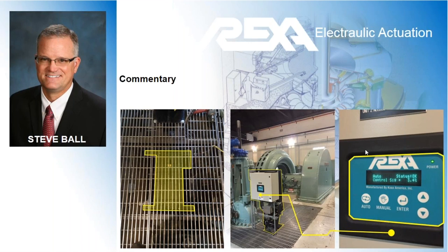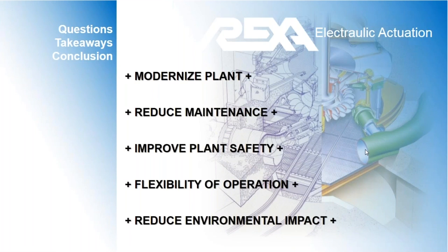We put another one of these together on the smaller plant on the other side of the Sierras, and its job was to modulate the power needle as well, with no governing, because it is a small unit tied to the system. It had a forebay up about 500 feet in elevation above the plant, and the idea was to maintain a set point at the forebay level. There was a float up there, and with a basic 4-20 system down to the plant, the REXA directly responds to that and holds the set point at the forebay. So it just matches whatever inflows to outflows. Anyway, back to the Rush Creek unit here.